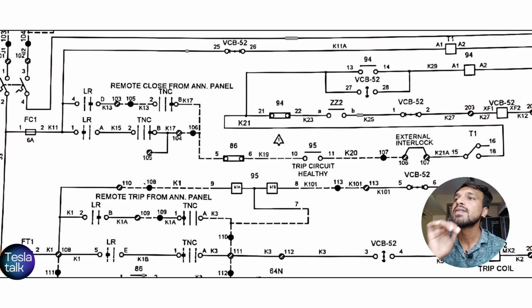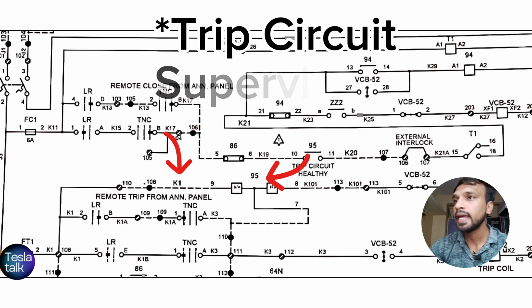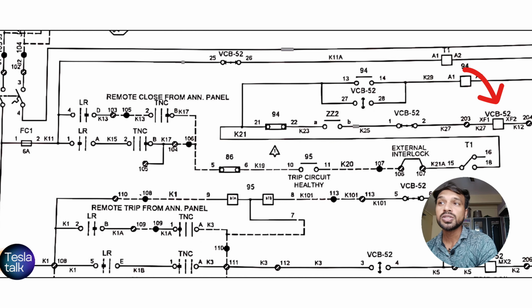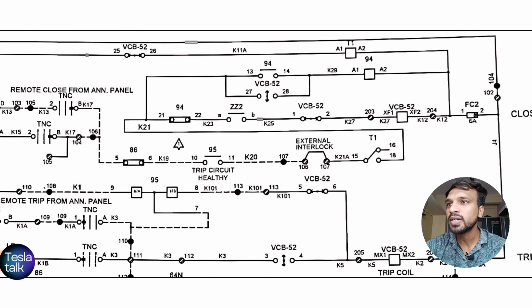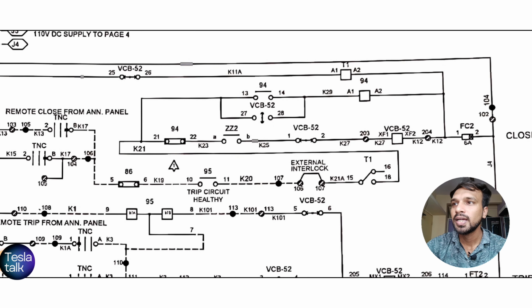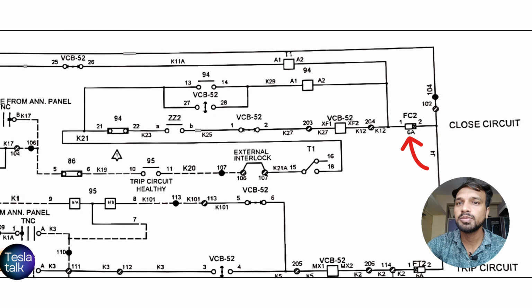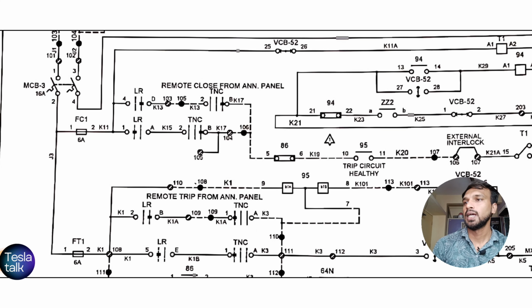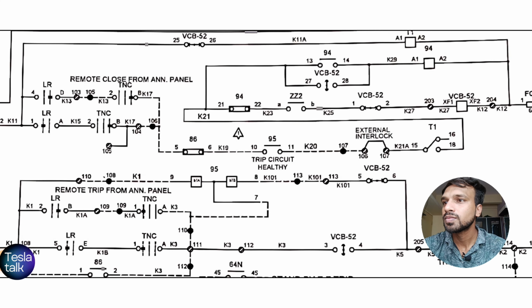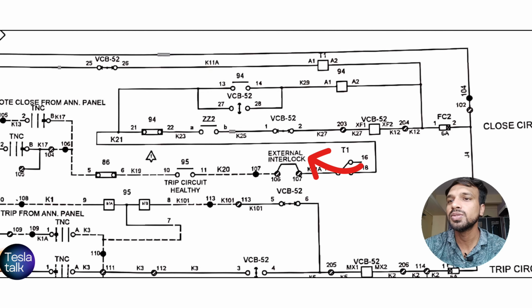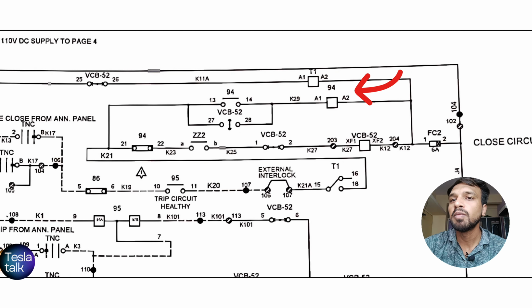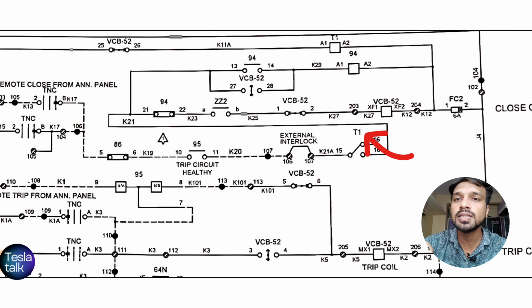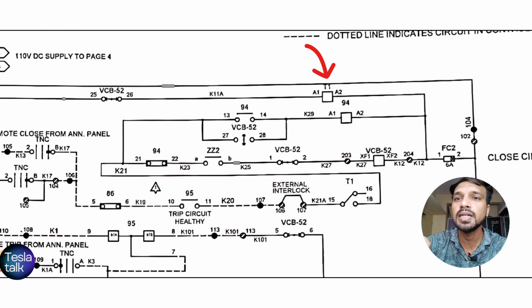Then this command is energizing the relay K1, which will initiate the VCB52 closing coil. The coil is energized through the relay contacts and protective fuses like FC1 and FC2, which will cause the breaker to close. So this one is the FC2 fuse and the FC1 fuse. You can see there are also interlocks used here, which is the 94 anti-pumping relay. And here one more thing is used, which is T1. It's a timer, and there is also a timer contact used. T1, this one is the timer contact, which is a changeover contact, and this one is the timer supply contact. And the VCB52 is the closing coil.